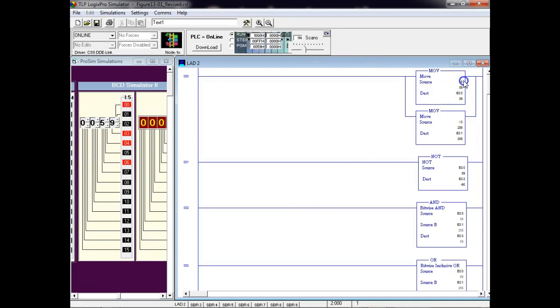So I can come over here now. Let's change this back because that's BCD. It'll be too hard to deal with. And we'll bring this back in from input 1 dot 0, right? So if you want to address a whole word, you put a dot, right? You understand? If you want to address a bit, you put a what? Slash. Guess what? For Siemens PLCs, it's just the opposite. So on Siemens PLCs, I'll use a dot if I need a bit. And no, we don't put a slash for a word. We specify a word in the instruction.